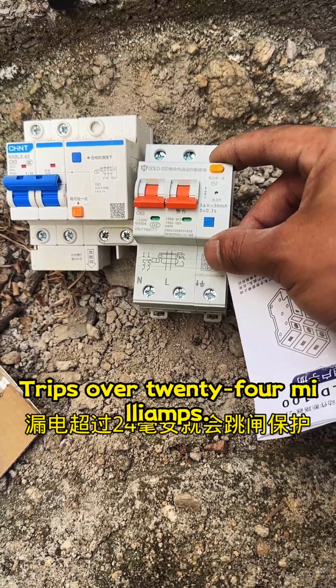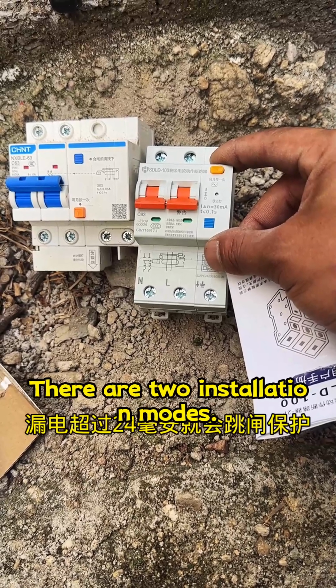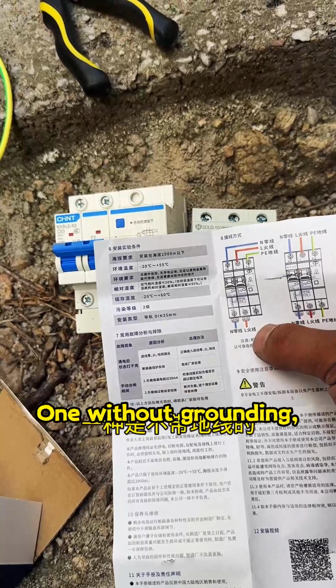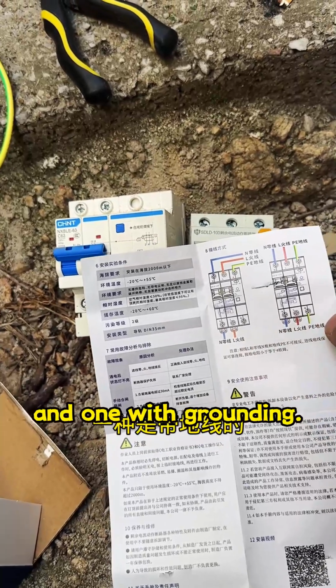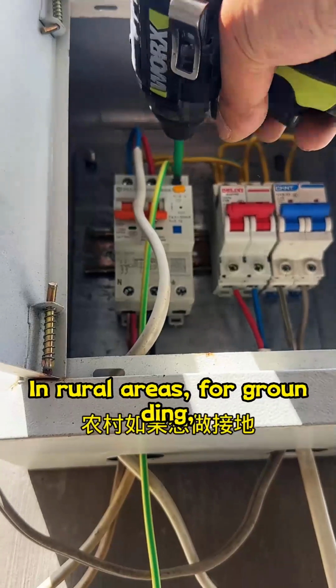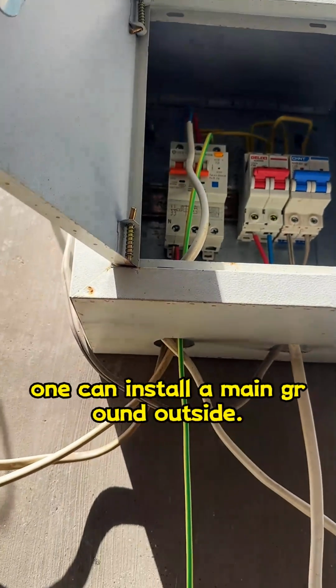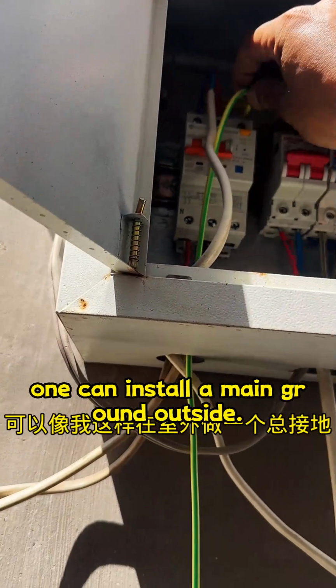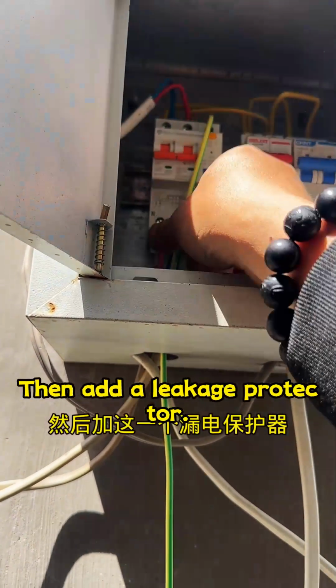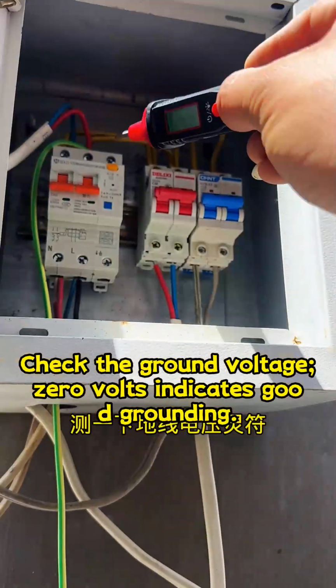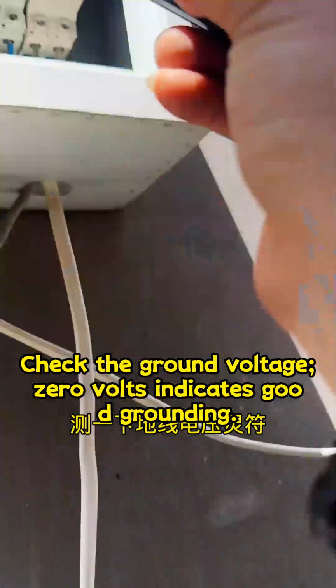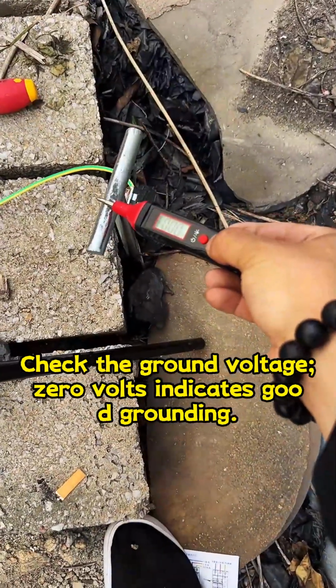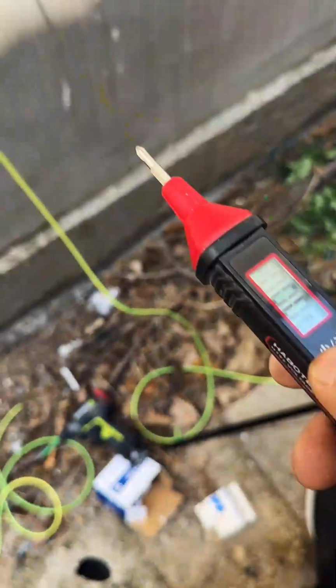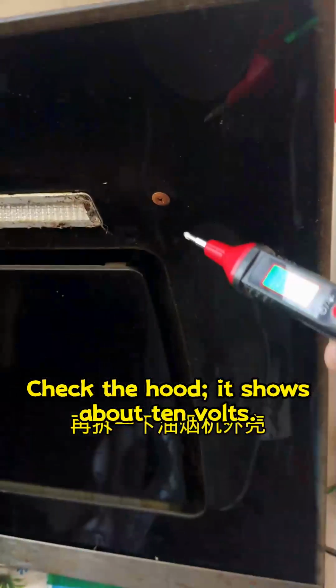Trips over 24 milliamps. There are two installation modes. One without grounding, and one with grounding. In rural areas, for grounding, one can install a main ground outside. Then add a leakage protector. Check the ground voltage. 0 volts indicates good grounding. Check the hood. It shows about 10 volts.